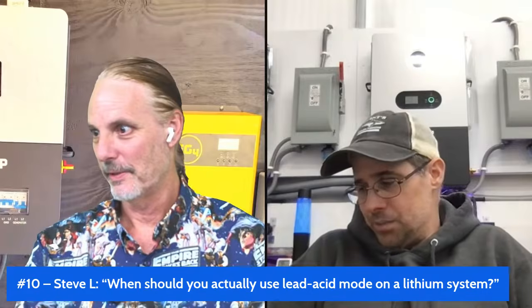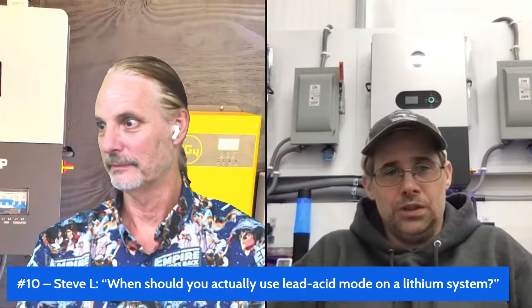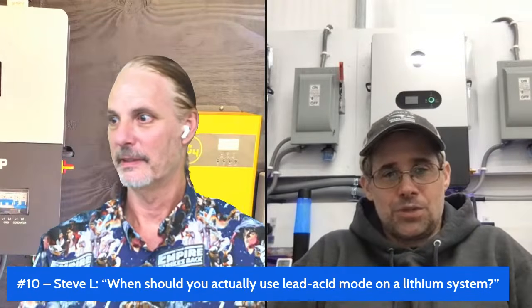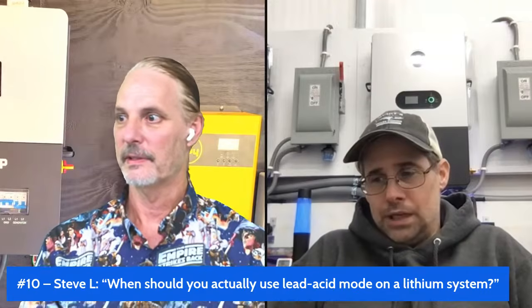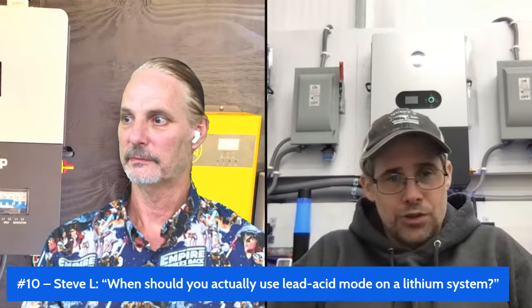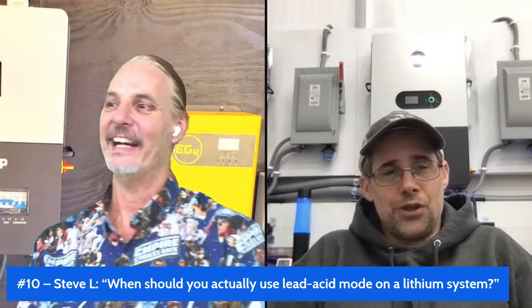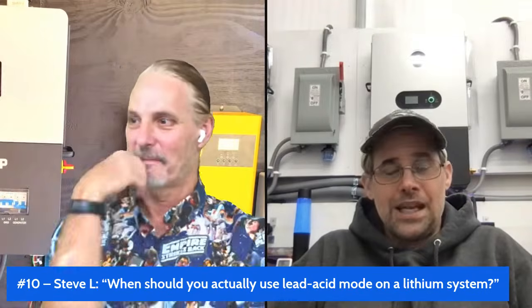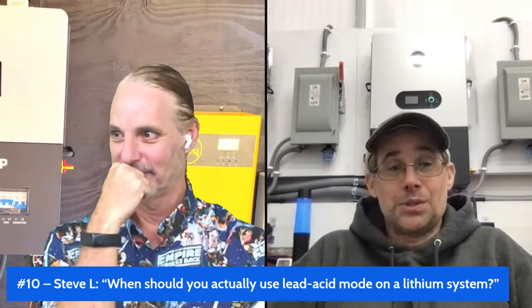And that's key that you bring up - they have to be within 1/10 of a volt. If there's a big difference between them, you will test the integrity of your wires. You will test if your breakers work or not, and your fuses. Do those pop?